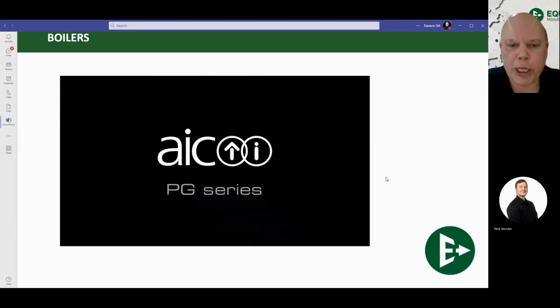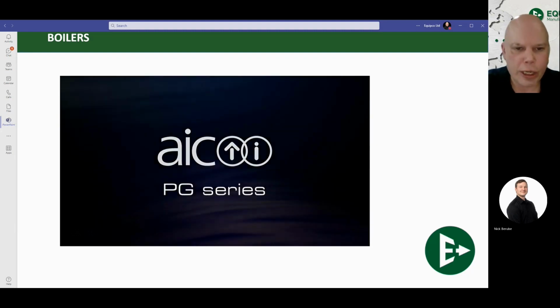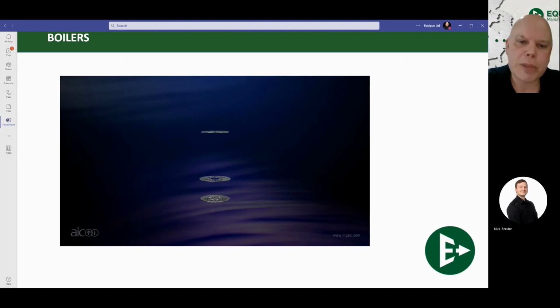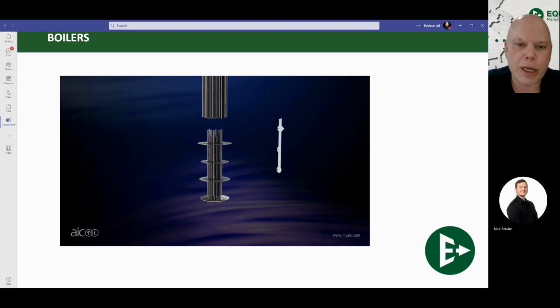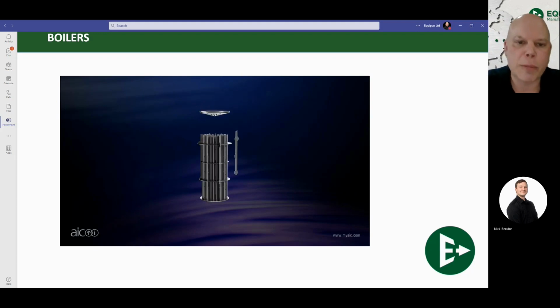Most fire tube heat exchangers now are made by a company called AIC, a wonderful heat exchanger. Most manufacturers of all boilers use these now. Here come down our spacer plates. This is what separates our fire tubes. Here they come right down there. That's where our flue gas is going to be coming through.